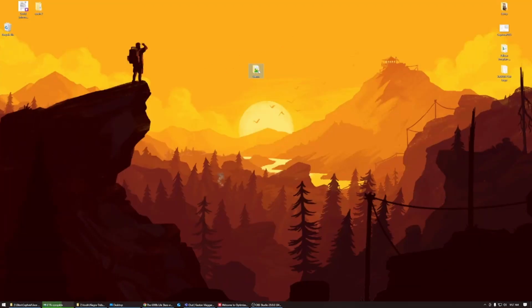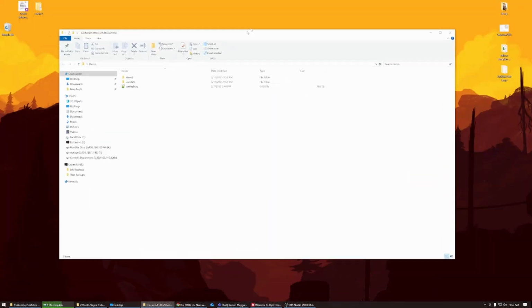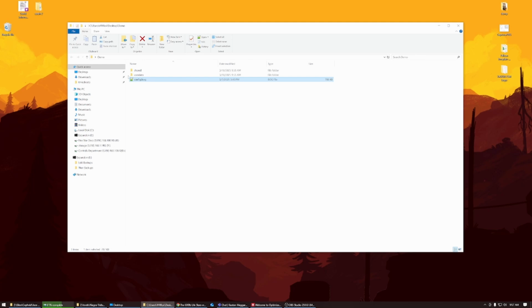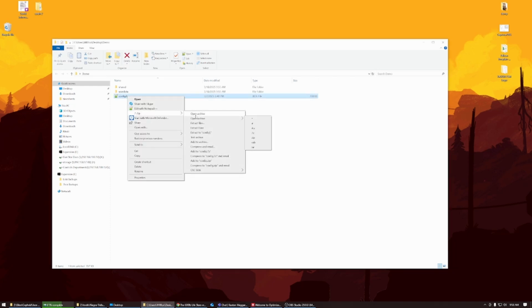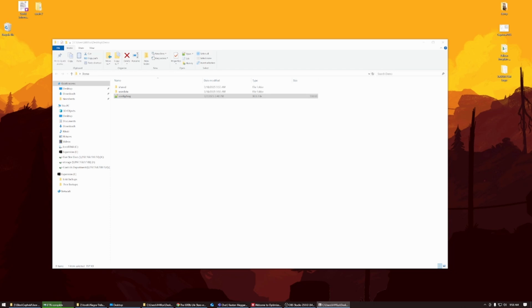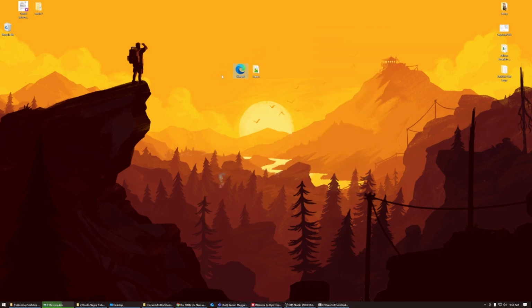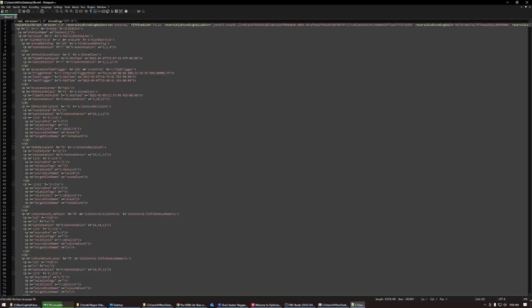First thing we do is go to the station folder and open it up. Inside the folder is config.bog. Config.bog is actually a zip archive. I use 7-zip to open my archives, so if we open that up with 7-zip, open archive, you'll get file.xml. If you take file.xml and pull it out onto somewhere to work on it, this is what we need to modify. So we're going to edit that with Notepad++.